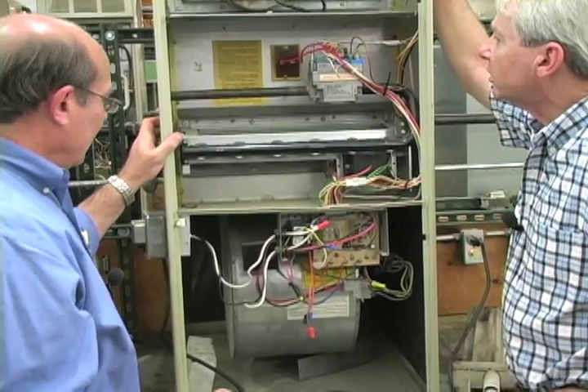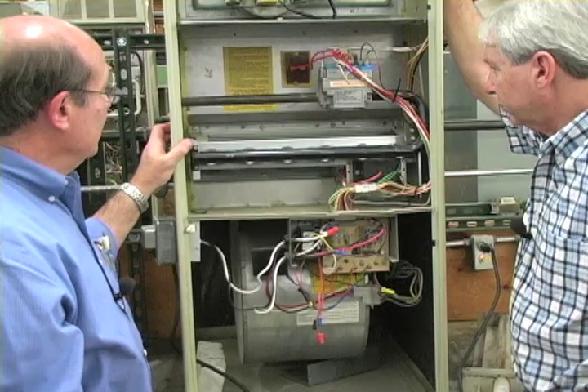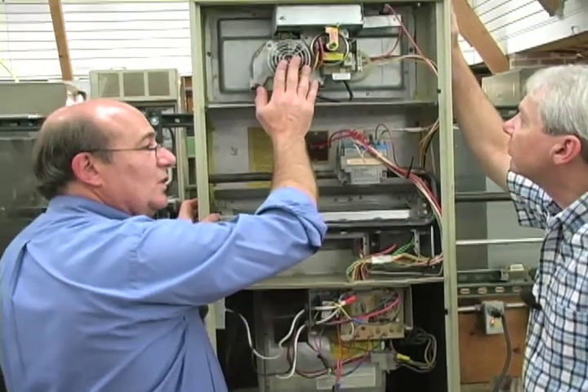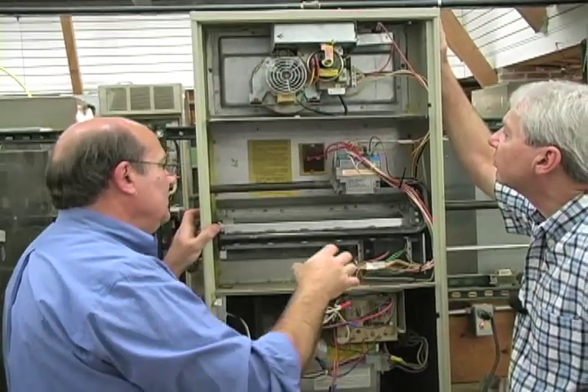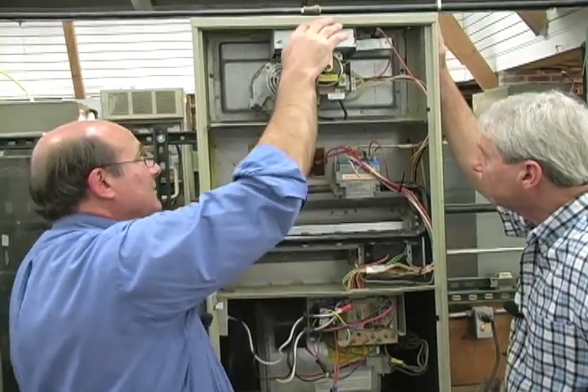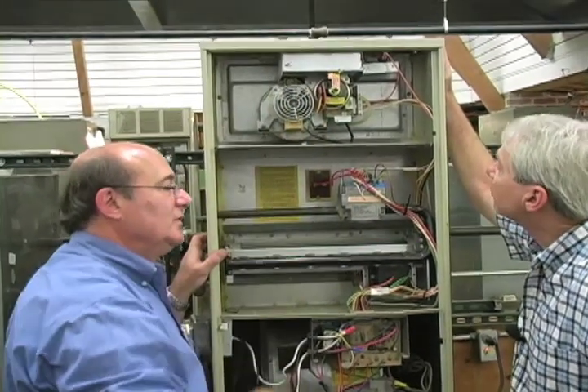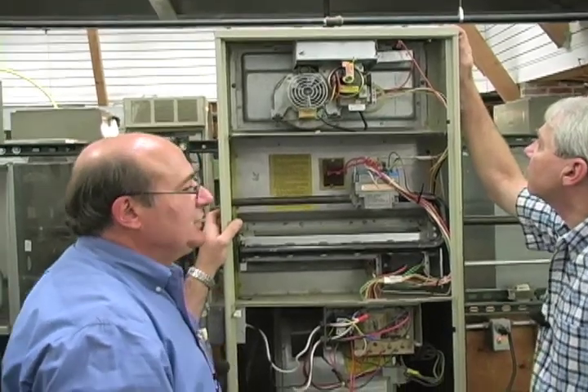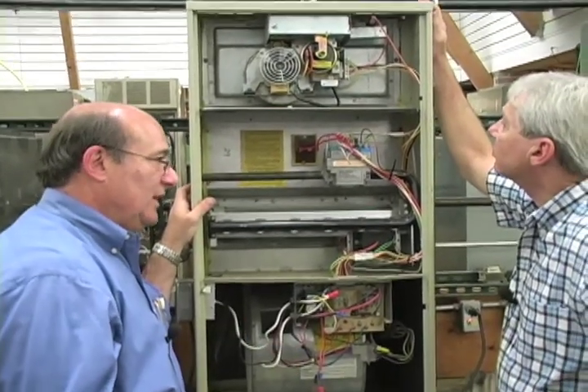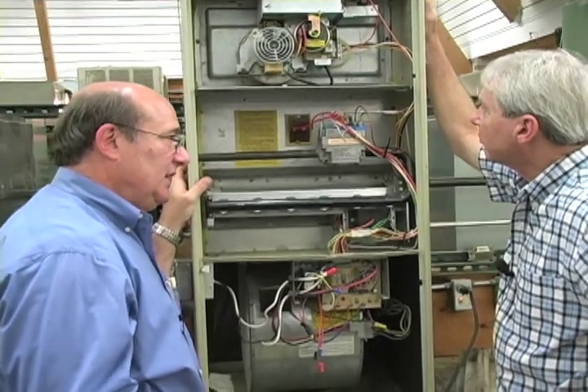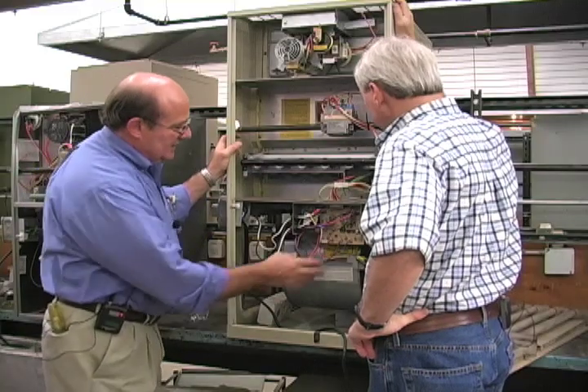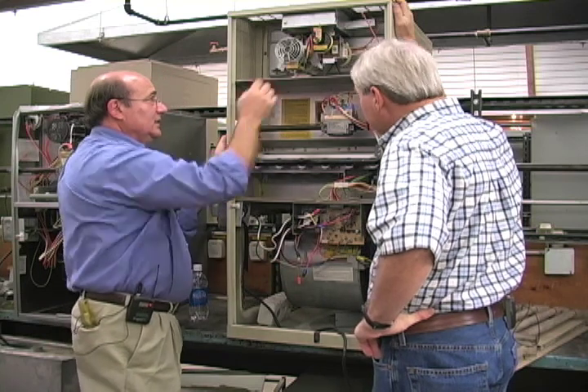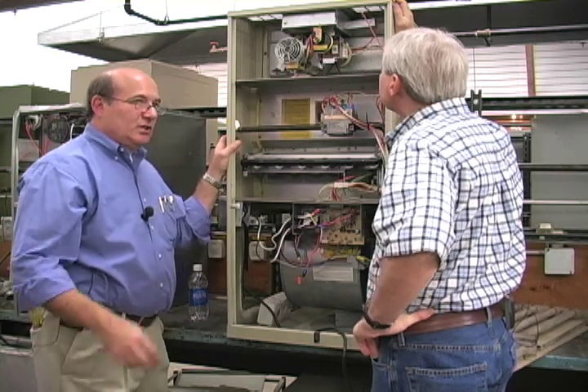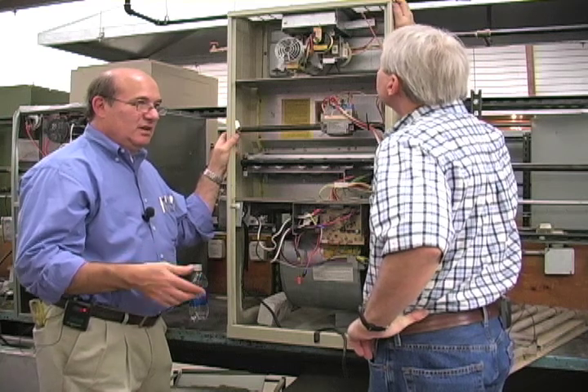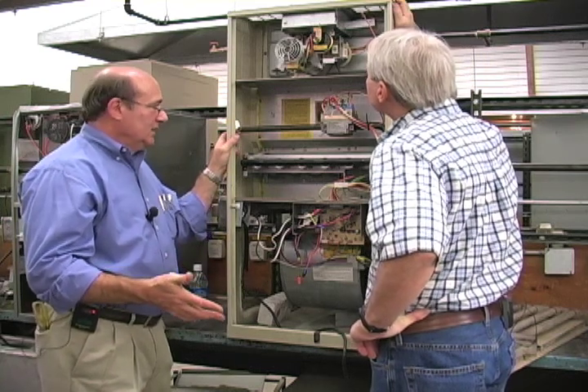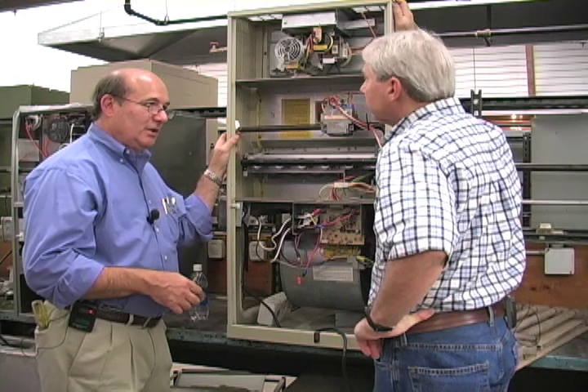So when we get a call for heat on a furnace like this, the first thing that'll happen is the combustion blower motor will come on. And that draws air through the heat exchanger and exhausts it up through the top, which will be vented up through the roof. And that's for the purpose of purging the heat exchanger, so that there's no residual gas left over inside there that might cause an explosion on the initial startup. Typically, this solid state board will bring this combustion blower motor on for some predetermined time period, 20 seconds, 30 seconds, and some of them are adjustable, so you can set those up wherever you want.